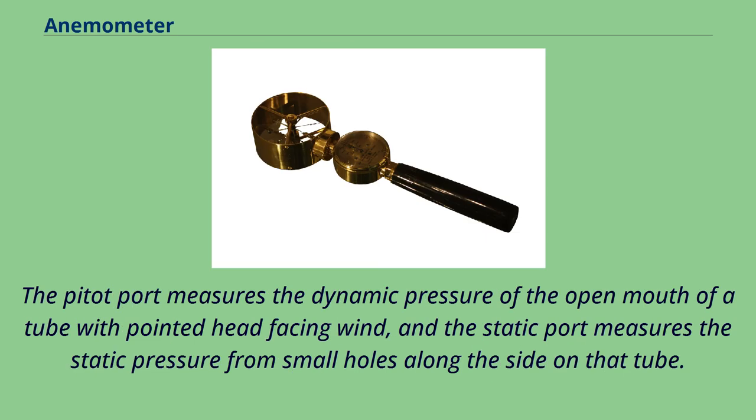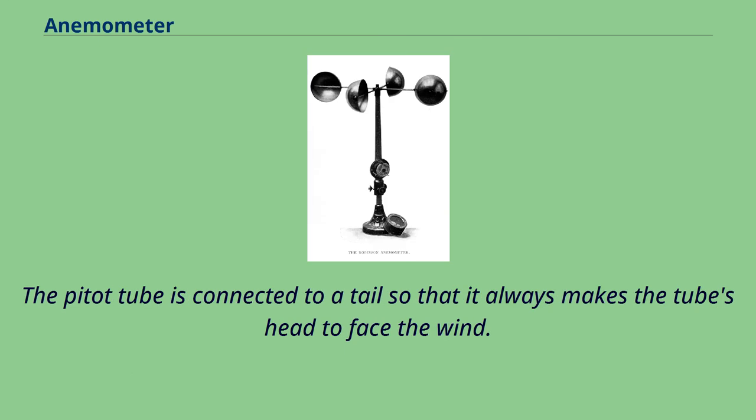Modern tube anemometers use the same principle as in the Dines anemometer but using a different design. The implementation uses a Pitot-static tube which is a Pitot tube with two ports, Pitot and static, that is normally used in measuring the airspeed of aircraft. The Pitot port measures the dynamic pressure of the open mouth of a tube with pointed head facing wind, and the static port measures the static pressure from small holes along the side on that tube. The Pitot tube is connected to a tail so that it always makes the tube's head to face the wind.